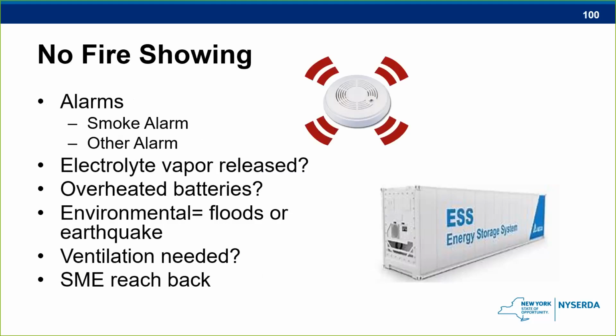So I'm just going to give you a little bit about what happens if you show up to the scene, no fire showing. You can see this container right here. The fire department may get a call to this type of enclosure, and maybe there was a smoke alarm that went off. So they show up to the scene and they say, well, I don't see anything showing. I don't see any heat source pointing my thermal imaging from a distance. So what do I do in that situation, right? Was there an electrolyte vapor released inside there, right? Is this a flammable atmosphere inside here if this smoke is not pushing outside? Because this is what we saw in Arizona, where they couldn't see anything. And they actually took their thermal imaging camera, they walked around, it was a structure, not a container, but they walked around the structure.